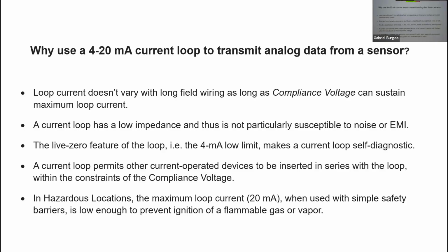Third thing about why do you use a current loop for networking? The live-zero feature of the loop, namely the 4 milliamps, it's offset from zero, gives you a self-diagnostic feature. If there's something wrong with the loop, let's say the current goes to zero, you know the loop is open somewhere. A wire is broken, a connection, something's unplugged or whatever. Or you get a very low number, you say, oh, there's a bad connection someplace, okay?